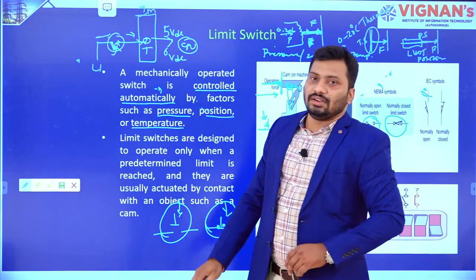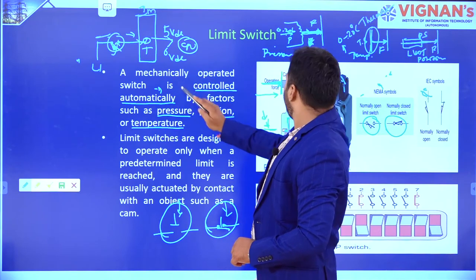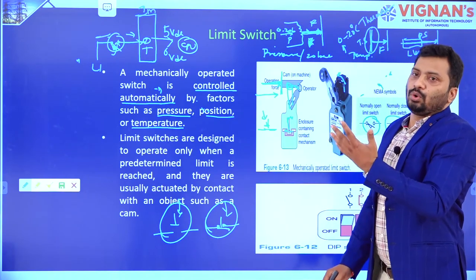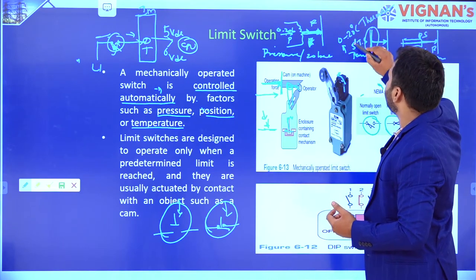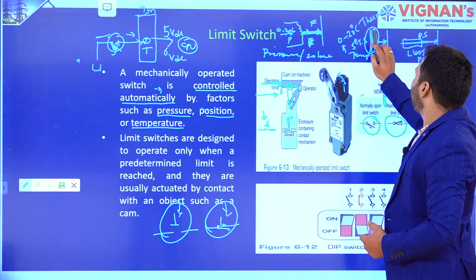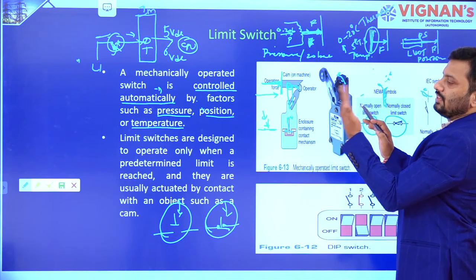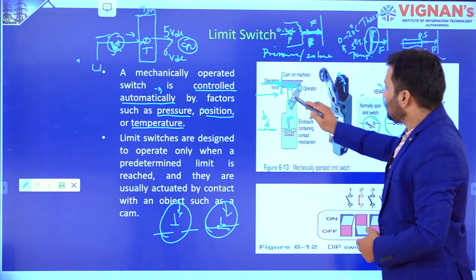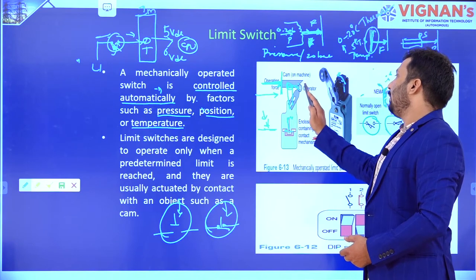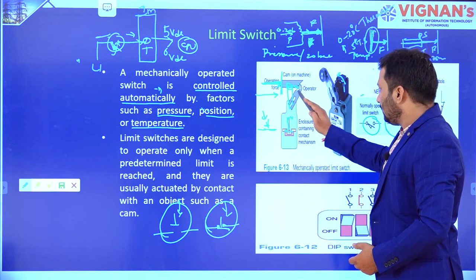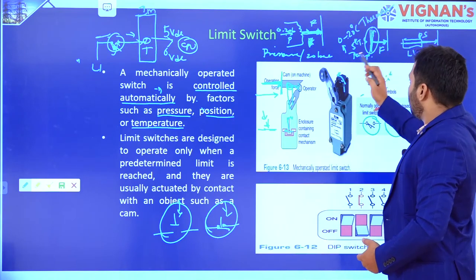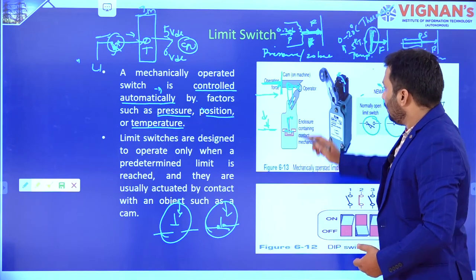The output is 0 volts DC — that is 0 volts as input to the CPU. The CPU understands that the temperature is less than 20 degrees. For example, at 5 degrees temperature, it is giving some force — the thermostat is bending a little bit, the bimetallic strip is bending, some force is going to act on this particular terminal. That means the cam, the actuating element, will move a little bit, but it is not going to be closed. It is in a partial position. Then if it increases to 15 degrees, it is in another position with corresponding force acting on that terminal.